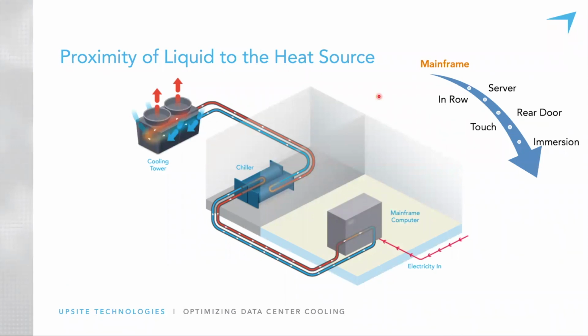Let's show you a number of pictures here. These programs talk about heat exchangers and ultimately immersion, and you'll see that the names and these dots here will change and indicate in orange where we are in this progression in this timeline. But for all cases, we've got electricity coming into the computer room, and that electricity is being consumed by some device. And as I said, every kilowatt of electricity becomes a kilowatt of heat that needs to be removed.